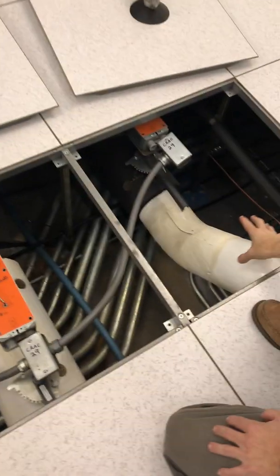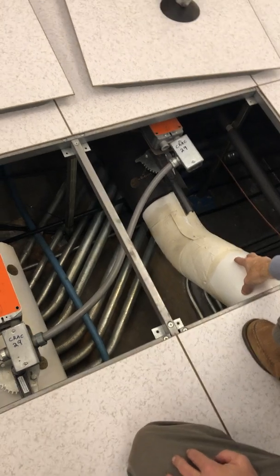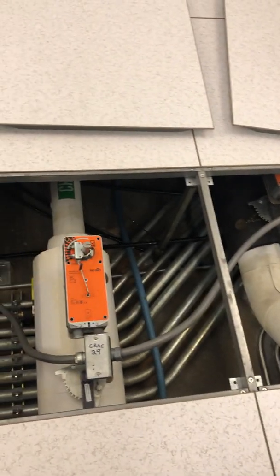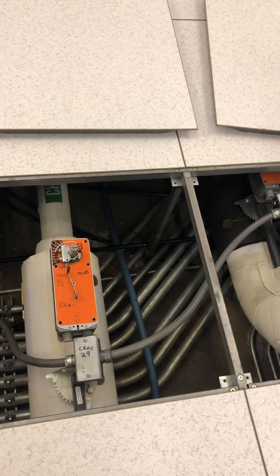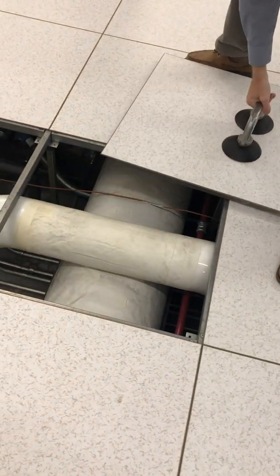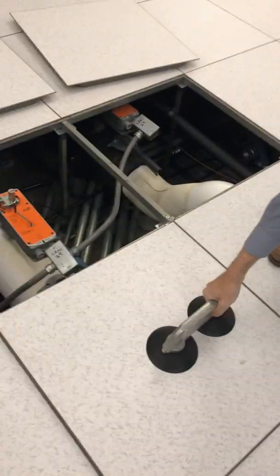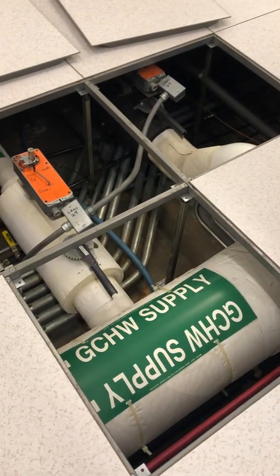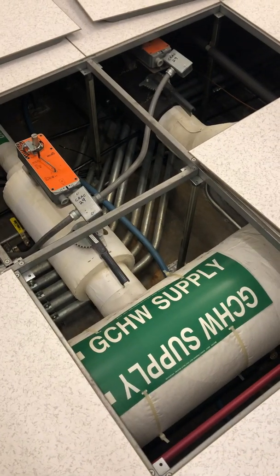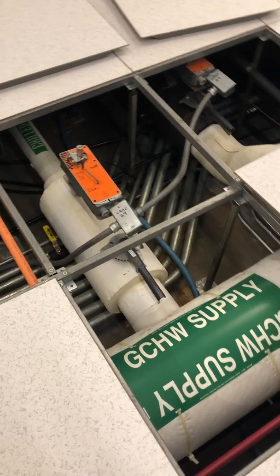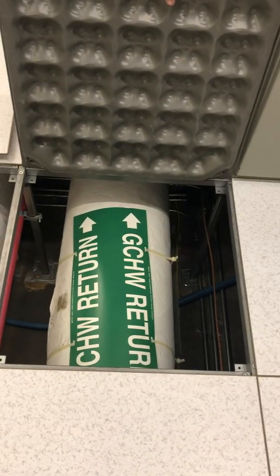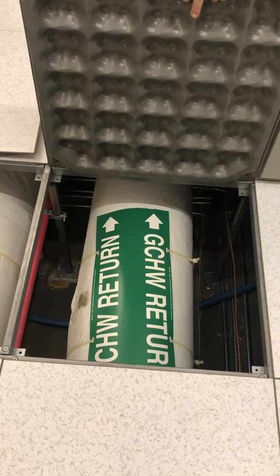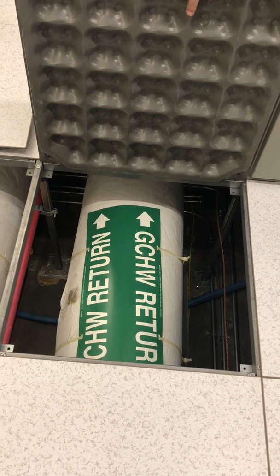What's under the floor here is that each one has a dedicated supply and return line that comes off the main trunk. The main trunk runs the entire perimeter of the room in a loop. I'll open the next one since it's got the labels on it. The supply runs around the room as the arrows indicate, and the return does the exact opposite. Those match up to the pipes we've seen in the receiving bay and then the chiller plant.